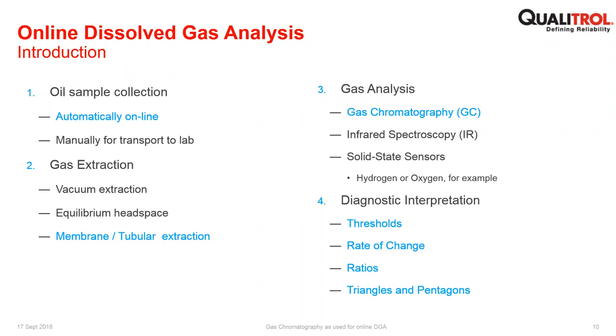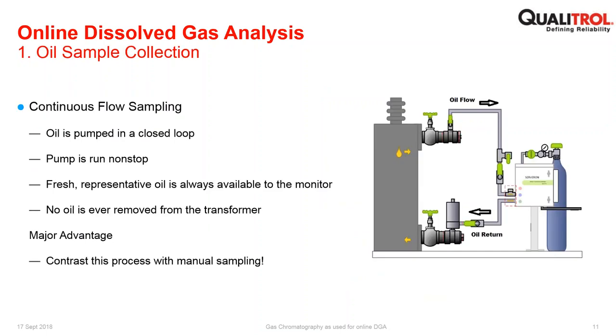And then, of course, once you have measured the gas, and ultimately this is the intention of online dissolved gas analysis, it's really all about diagnostics. So you look at thresholds, at rate of change, at ratios of gases. There are Duval triangles and pentagons that are universally known as a technique for interpreting these results, because ultimately what we are not trying to do here is to gather data on ppm, parts per million, of dissolved gas. We're trying to interpret what's the condition of the transformer or the piece of electrical equipment. So diagnostics is, of course, the ultimate goal of all online or offline dissolved gas analysis.